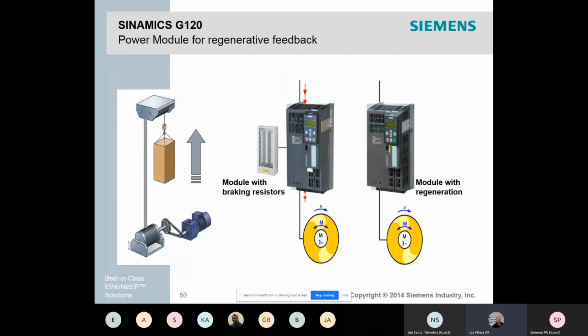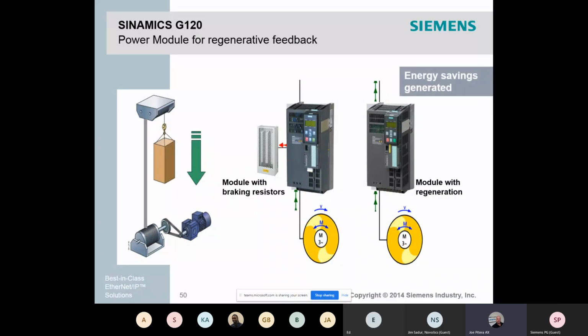A unique feature in the power module with regenerative feedback is this: in a module without regenerative feedback, braking resistors are normally used in case of energy generation on braking or emergency stops. Energy would be dissipated as heat in the resistor. However, when using a module with regeneration, the energy is returned to the power grid. That way you can save on energy, the resistor space, and you can reduce panel temperature. Most other vendors do not offer an integrated regenerative solution.